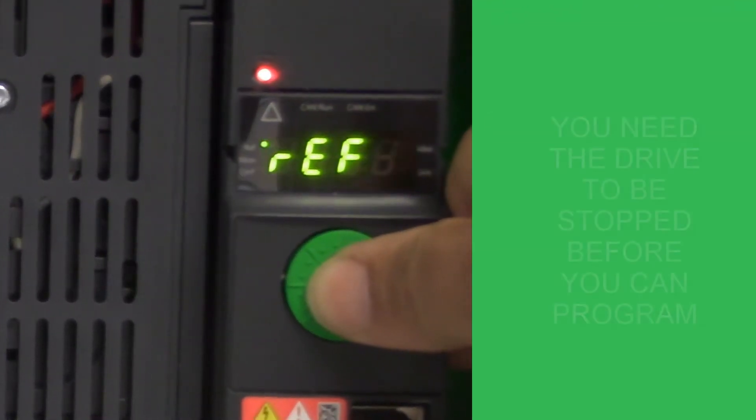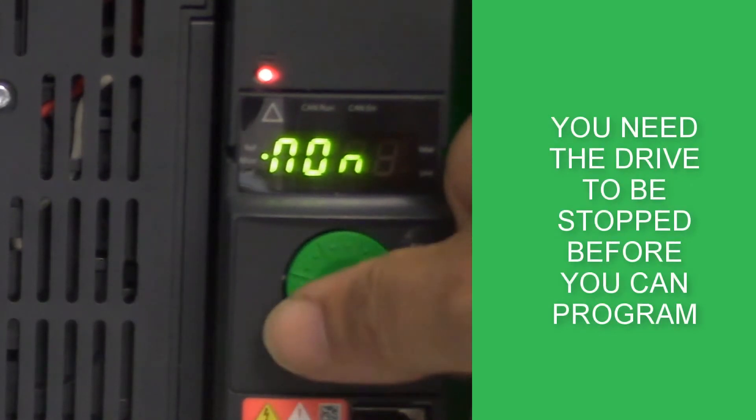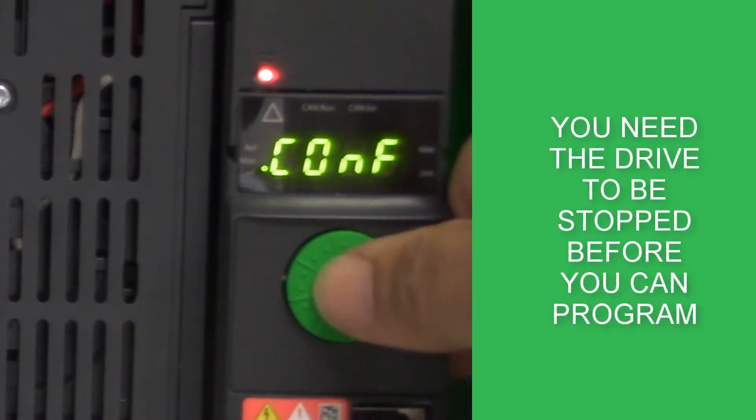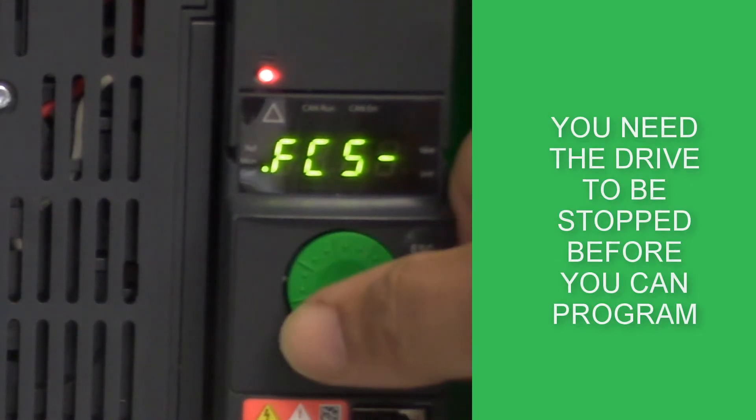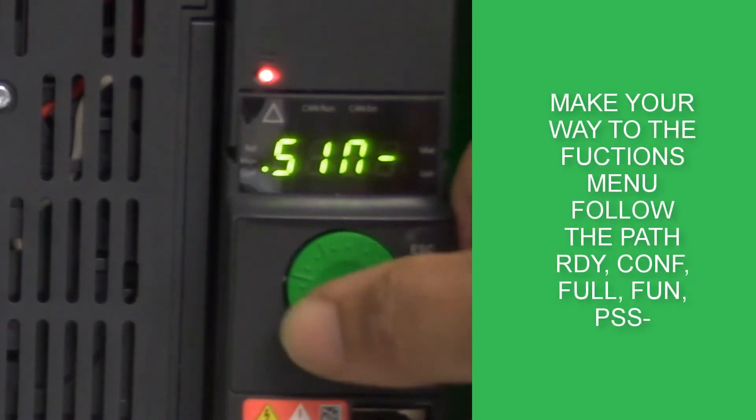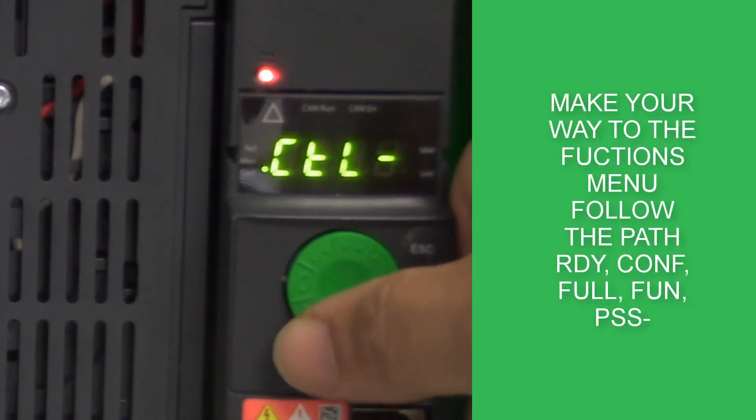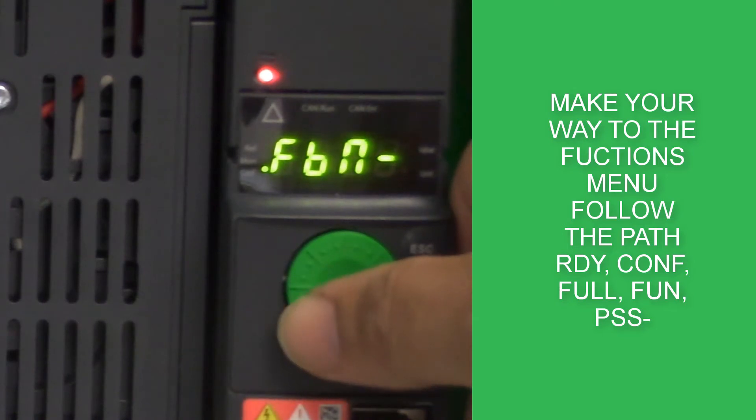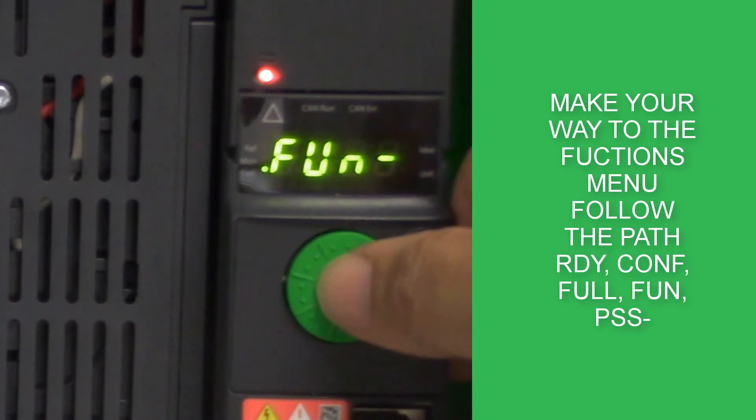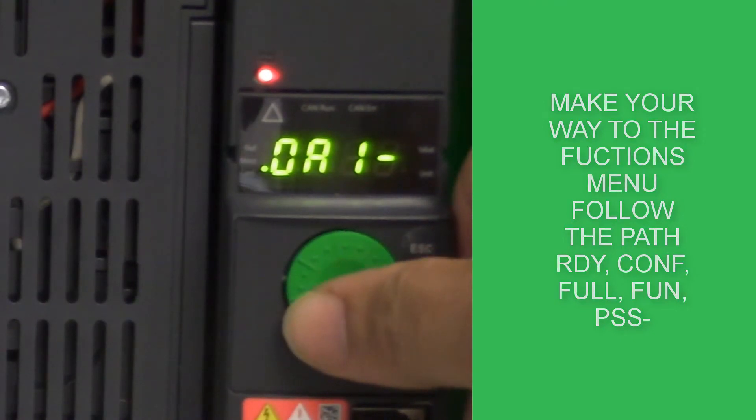Start from the ready position, press enter, go to CONF, press enter, go down to FULL, press enter and go down to the function menu and press enter. Once in the function menu, scroll down to the preset speed menu, PSS with the minus sign.